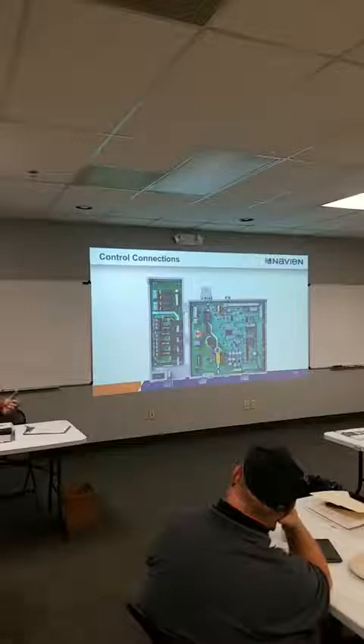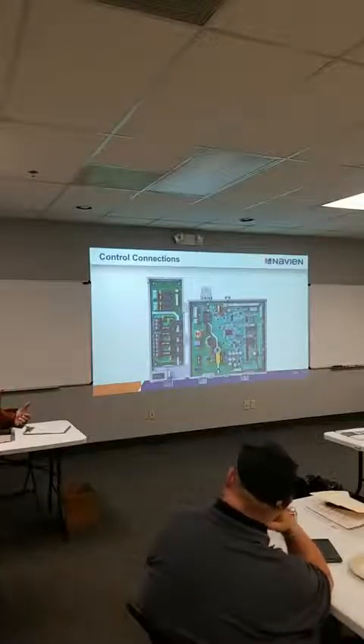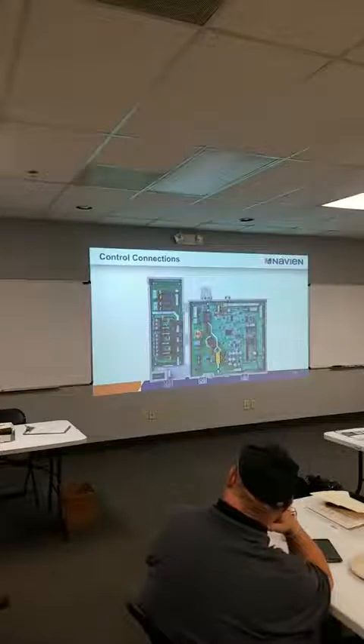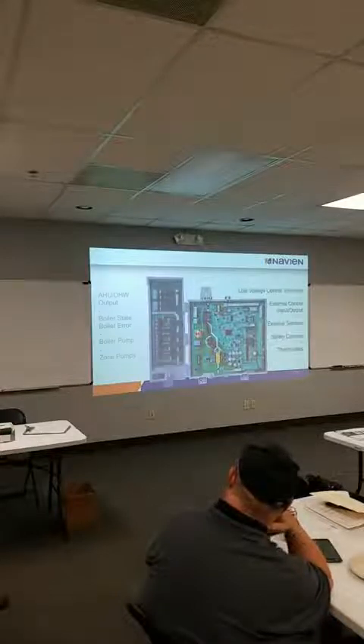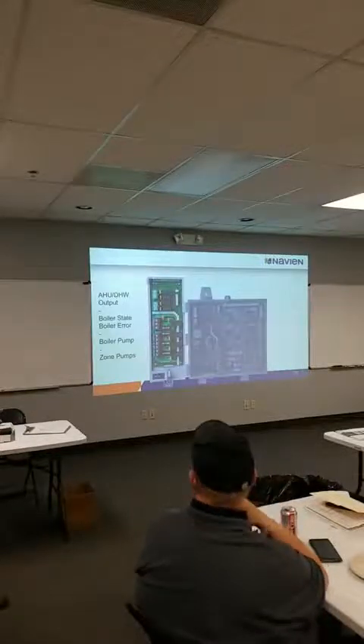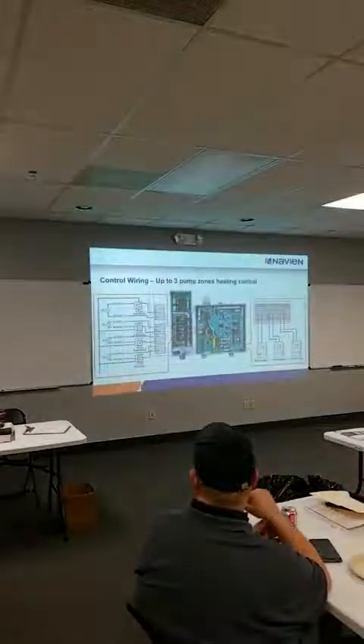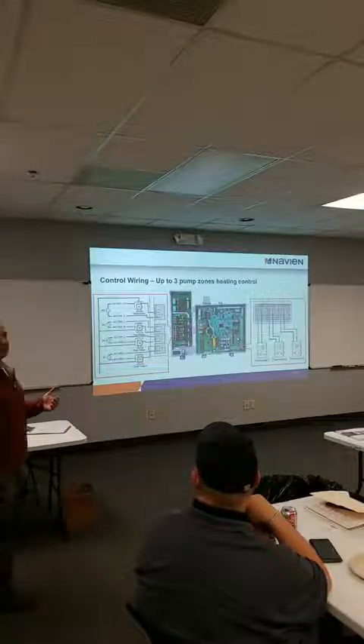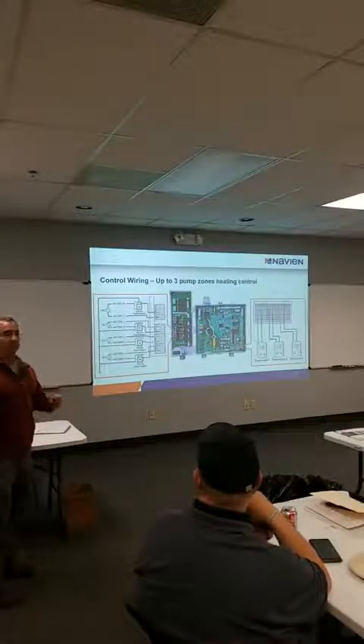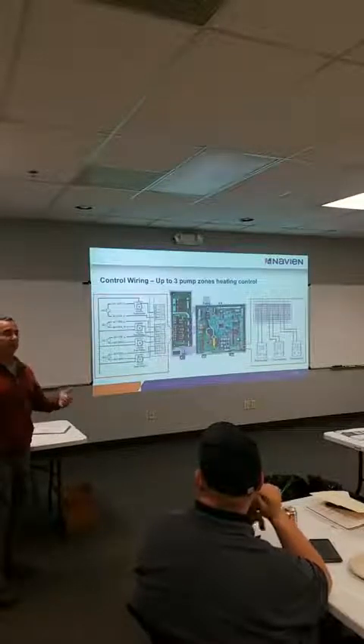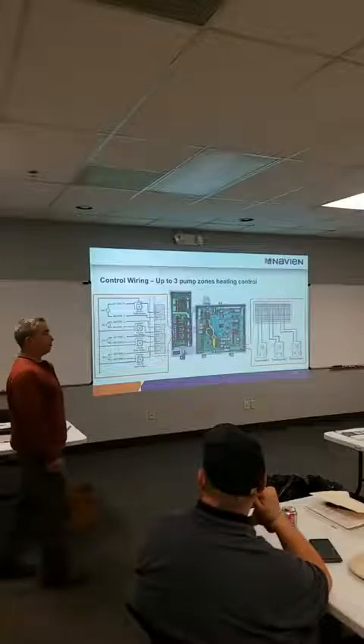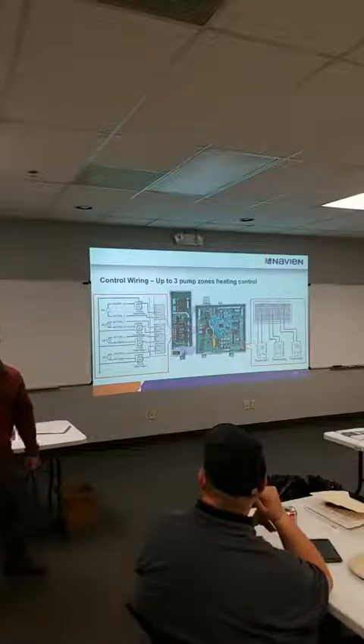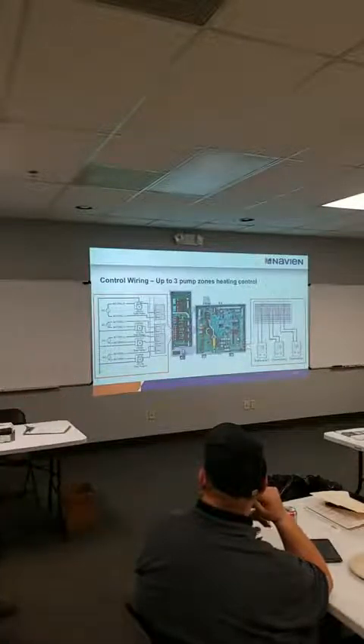This only does zone pumps right now, all right, and we cannot power those pumps from our board. Because we don't know what size system pumps you're gonna be using, or what size system pumps are out there. We can only activate those pumps on and off. So you got a digital output port, or you can use a panel, if you wanna use a panel and wire it back.